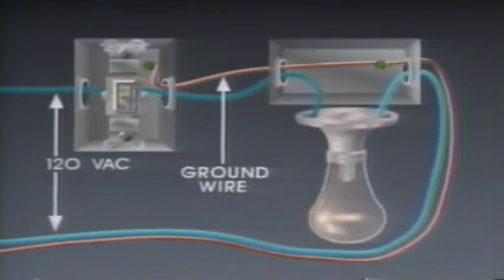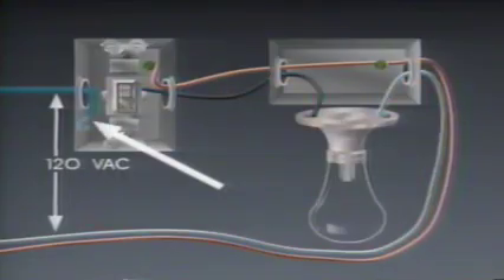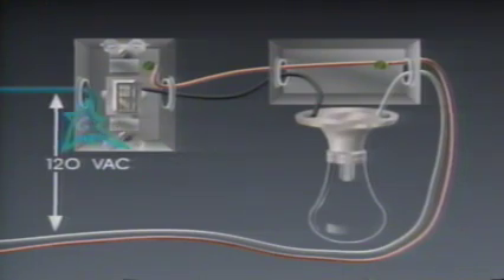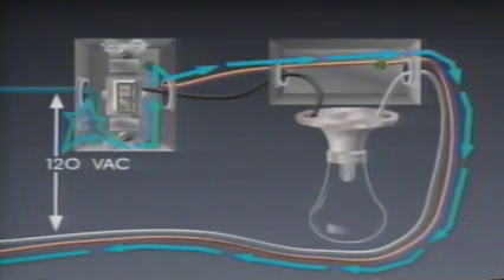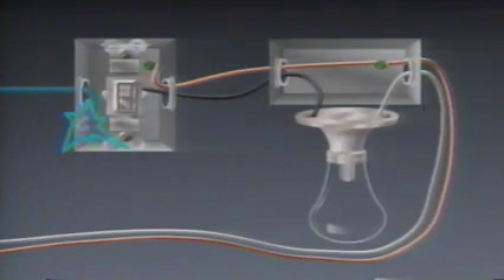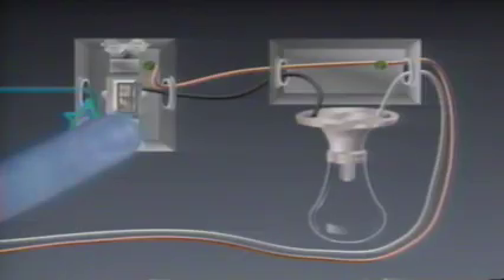The ground wire is provided in case the hot wire is accidentally broken or becomes exposed and touches something that is capable of conducting electricity, such as a junction box, a switch, or a receptacle, creating a short circuit. Short circuits can be very dangerous situations. If, for example, an electric switch becomes shorted and someone touches it, the electric current could attempt to complete the circuit through the person's body to ground.